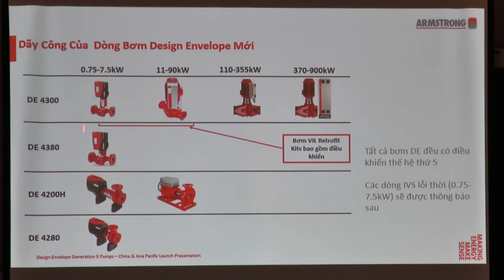Here you can see for these power ratings, we will be succeeded by our generation 5 pumps. These pumps will use our DEPM motors. DEPM means the design envelope permanent magnet motors with IE5 efficiency. And for those above 10 horsepower, such as the DEVIL, this would be this type. And we also have the DEPC card for this. This is the newest upgrade, and also for those larger sizes. And for those Gen 3 pumps who want to upgrade to Gen 5, we can replace them with a retrofit kit with the DEPC card to upgrade the Gen 3 pumps to our Gen 5 pumps.